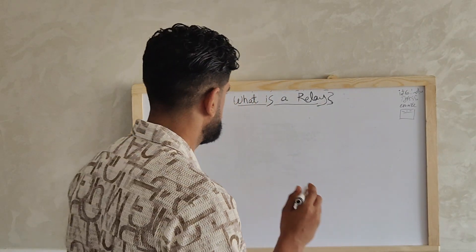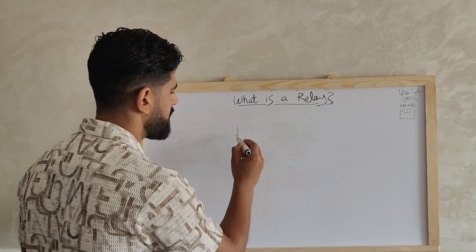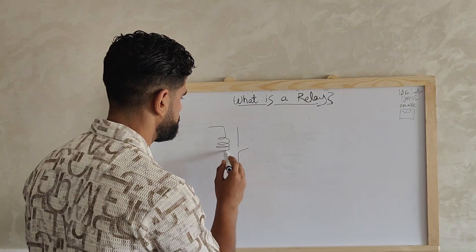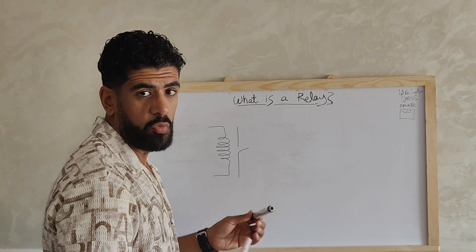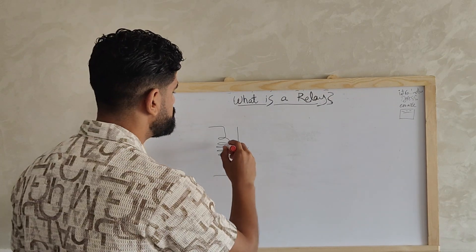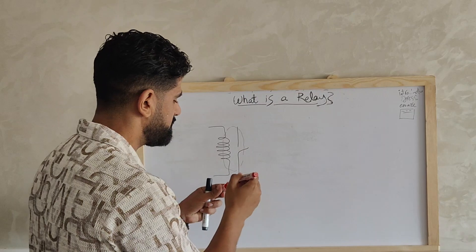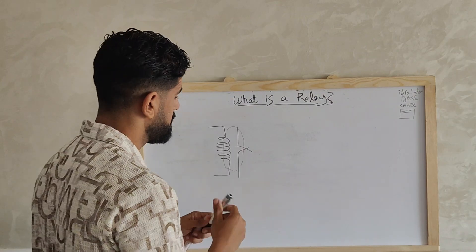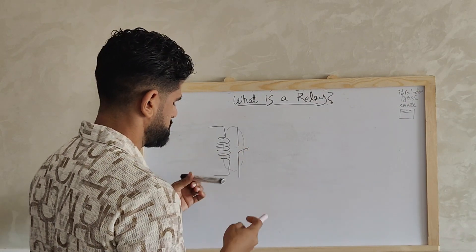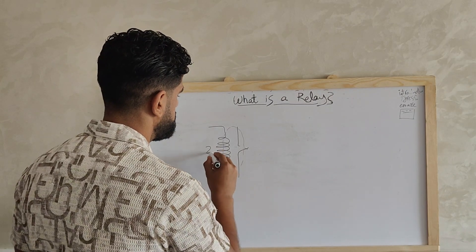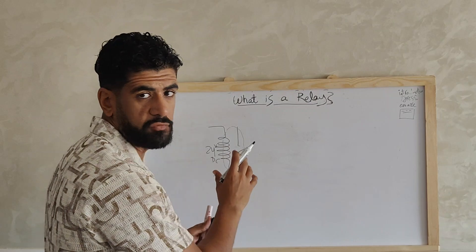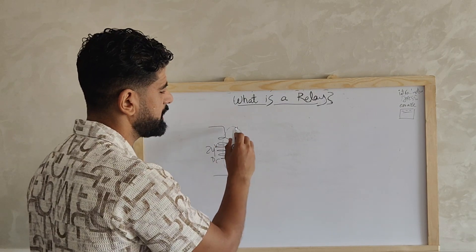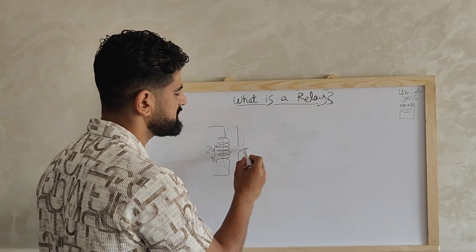An electrical relay is a switch that connects two points to each other. Inside the relay we have a coil. This coil, when it's energized, will generate an electromagnetic field that will attract this switch to be closed. Let's say that this coil is 24 volt DC — it has a rated voltage of 24 volt DC — so when we apply 24 volt DC to this coil it will generate an electromagnetic field and will let this contact be closed.